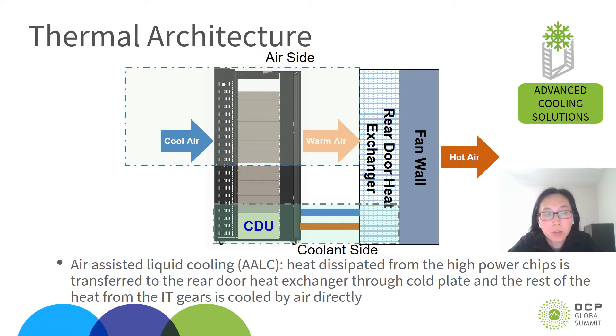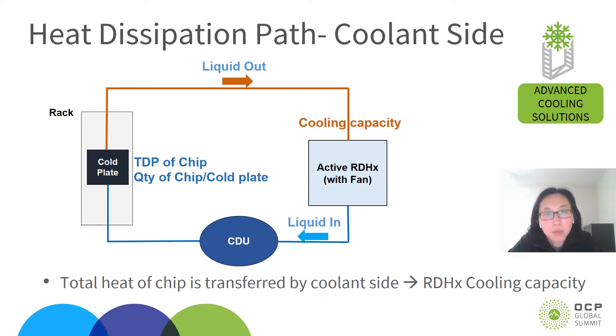At the thermal architecture level, it is an air-assisted liquid cooling (AALC) system, which means the heat dissipated from high-power components such as the CPU and GPU is transferred to the rear-door heat exchanger through cold plate. The other heat from the IT gears is cooled by air directly. The coolant going through the cold plate in each chassis carries the hot heat from the major heat components such as the CPU and GPU, then goes through the rear-door heat exchanger to reduce the temperature, and is pumped through the coolant distribution unit and back to the cold plate. The cycle continues.